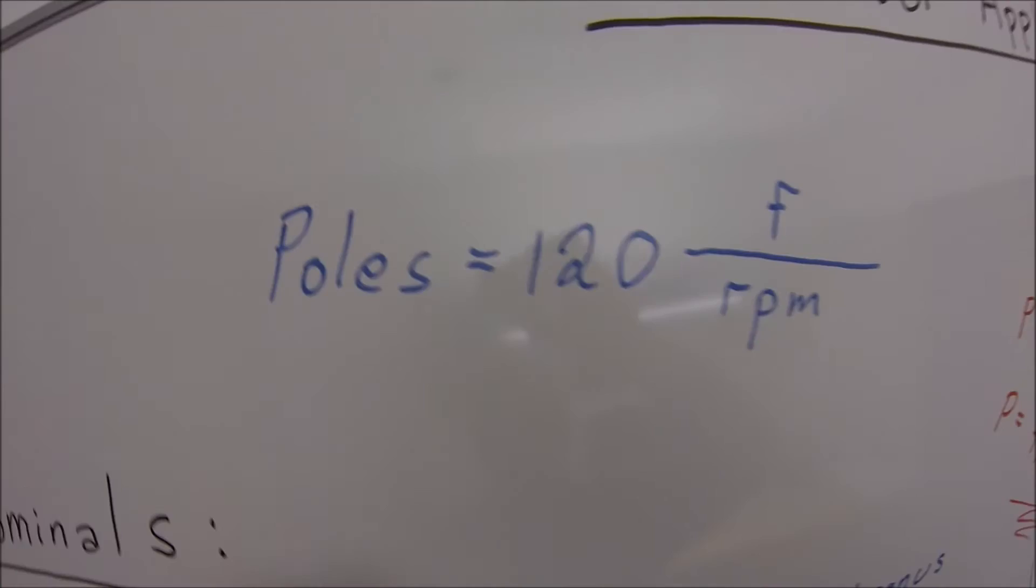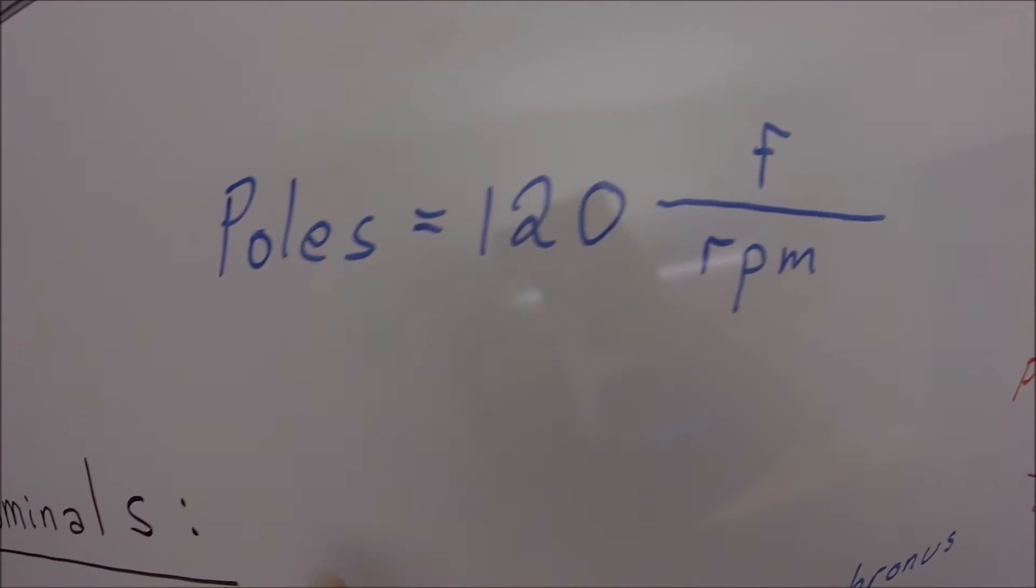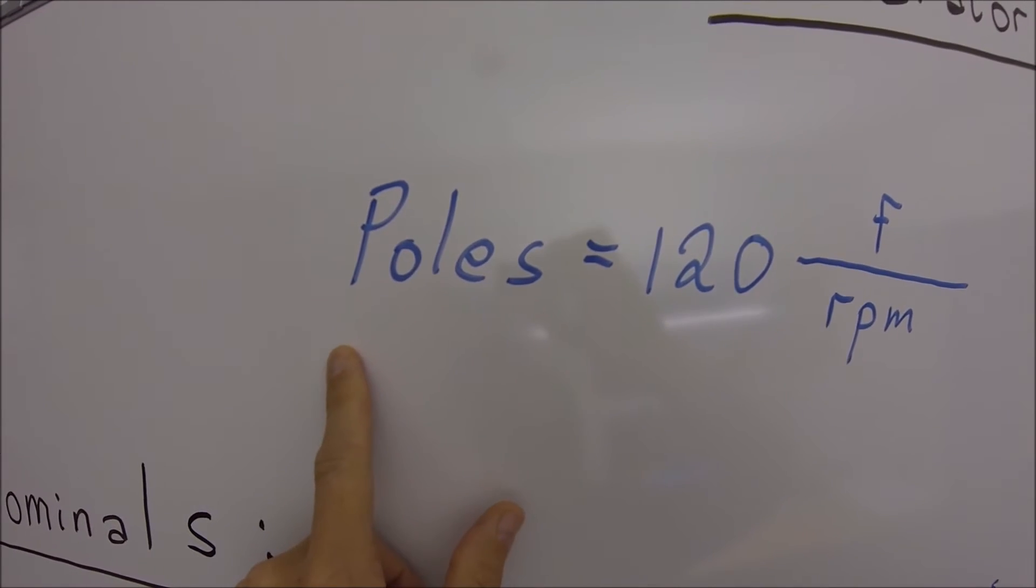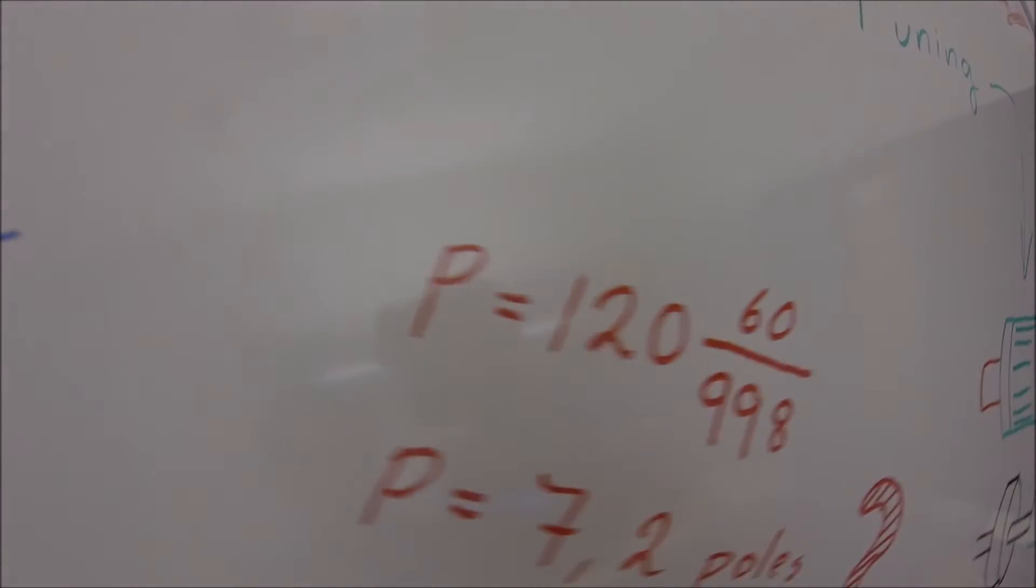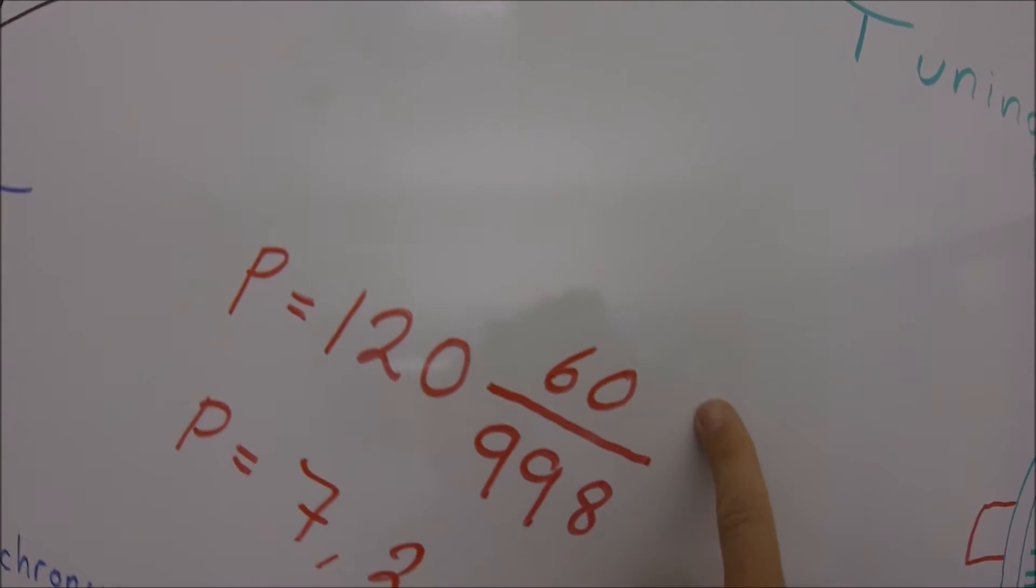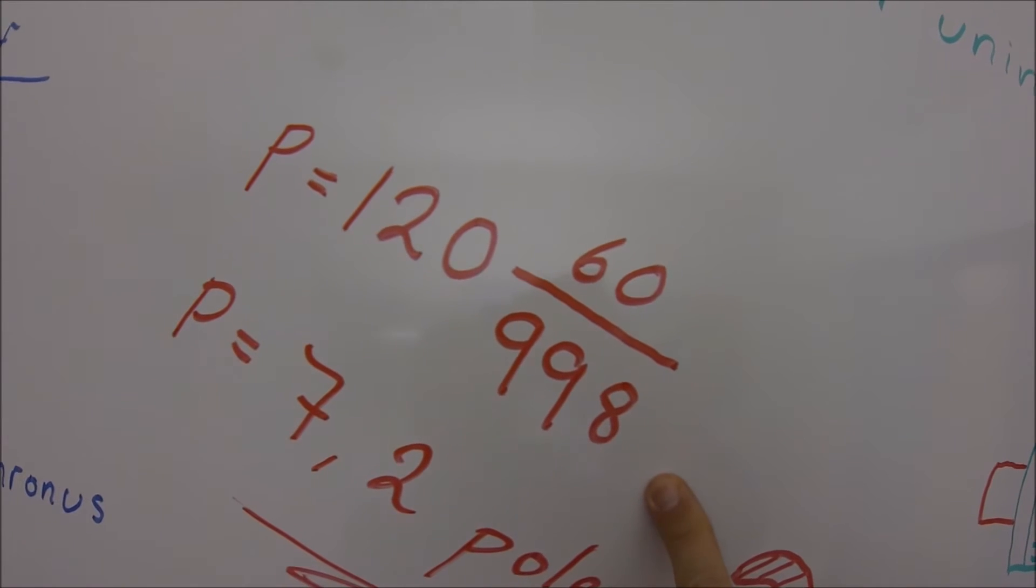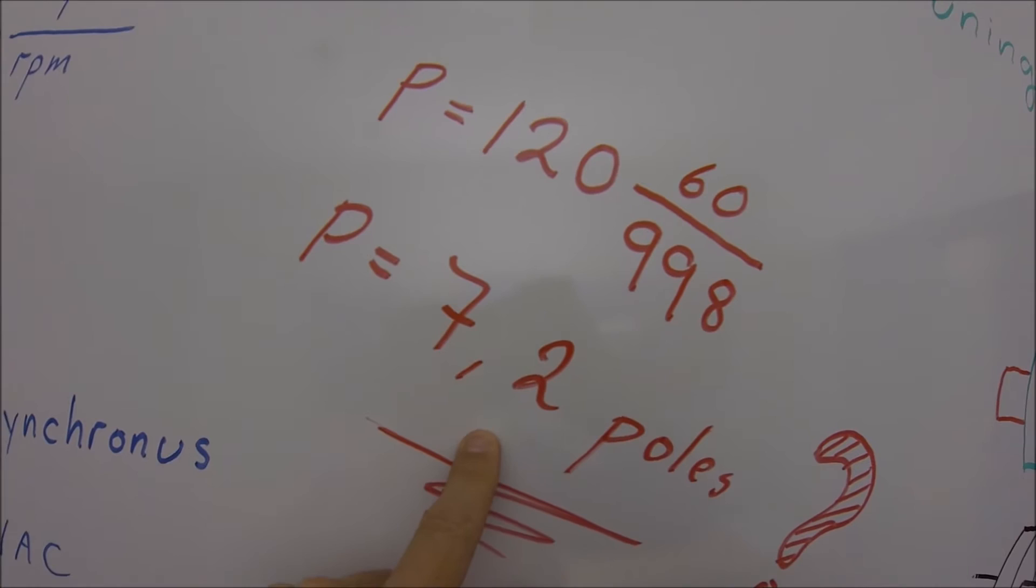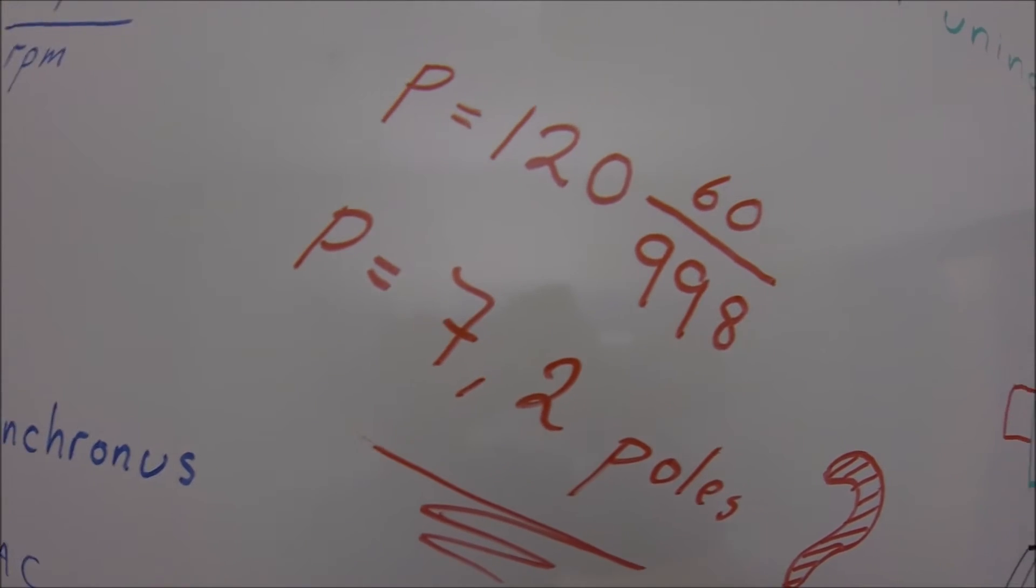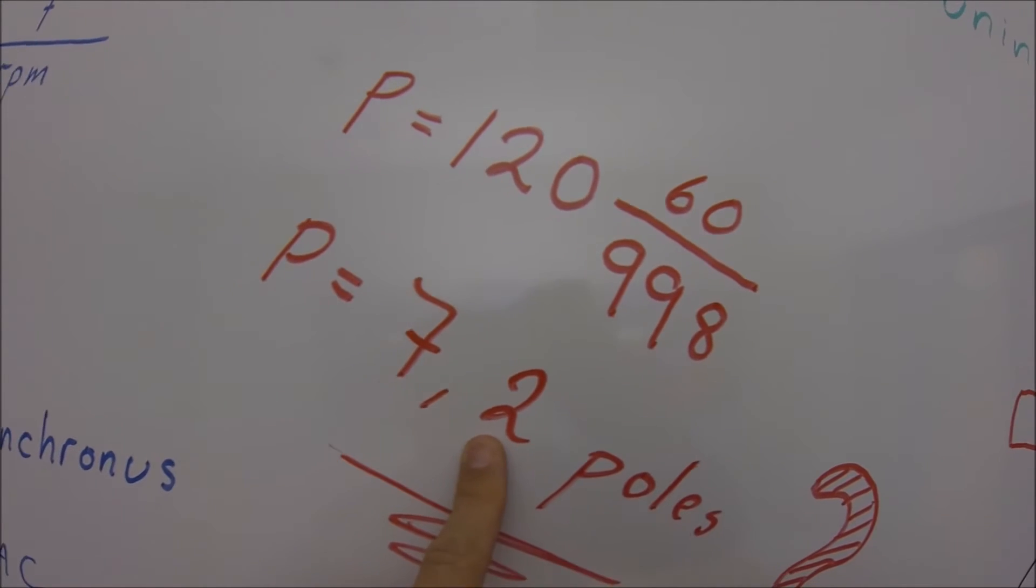The relation between the frequency and RPM will give the pole number. If I put these numbers into the equation, something strange: 60 hertz, 998 rpm, 7.2 poles cannot be right. It should be some number without decimals.